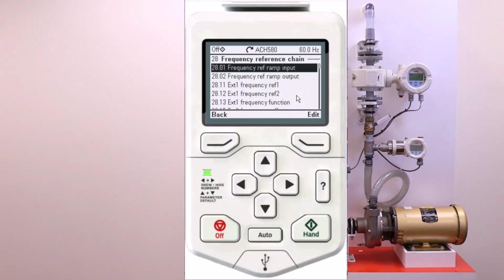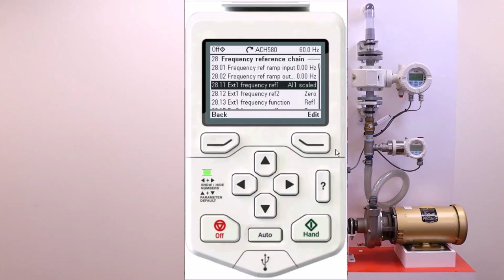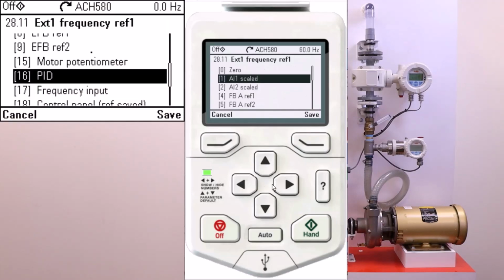Go to edit, and right now my frequency is set to analog input 1 scaled, and that's not what we want. We want to set this to our PID loop. We're going to go down to frequency reference 1, edit, and set this to PID. And this will be our first PID loop. Right there, save.